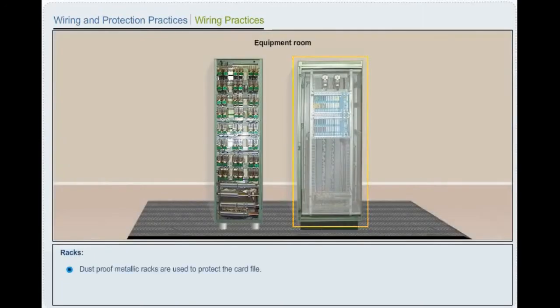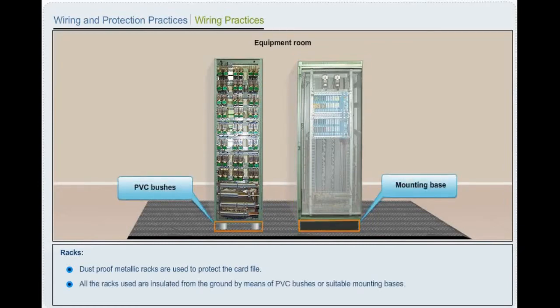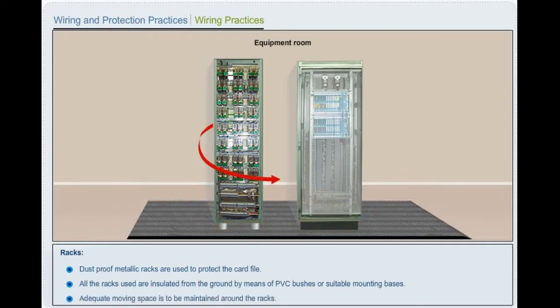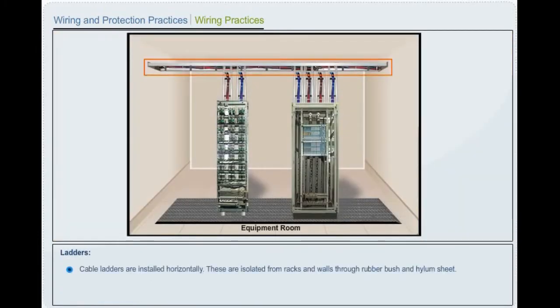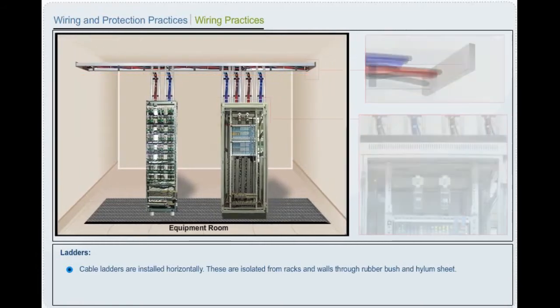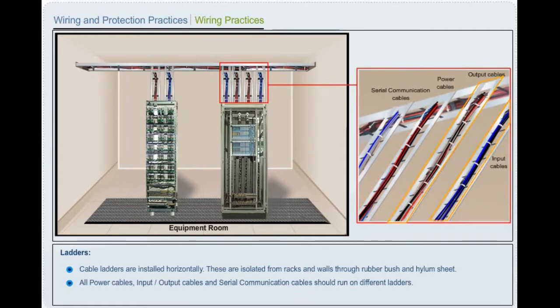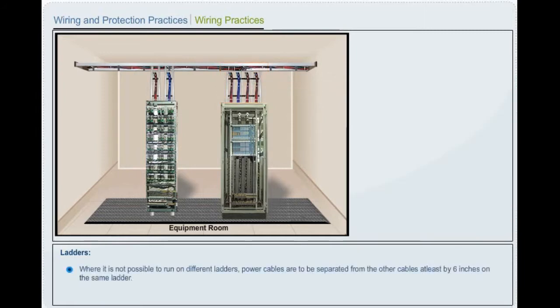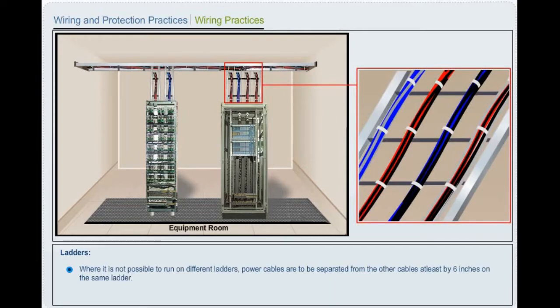Racks. Dust-proof metallic racks are used to protect the card file. All the racks used are insulated from the ground by means of PVC bushes or suitable mounting bases. Adequate moving space is to be maintained around the racks. Ladders. Cable ladders are installed horizontally. These are isolated from racks and walls through rubber bush and Hylam sheet. All power cables, input cables, output cables, and serial communication cables should run on different ladders. Where it is not possible to run on different ladders, power cables are to be separated from the other cables at least by 6 inches on the same ladder.